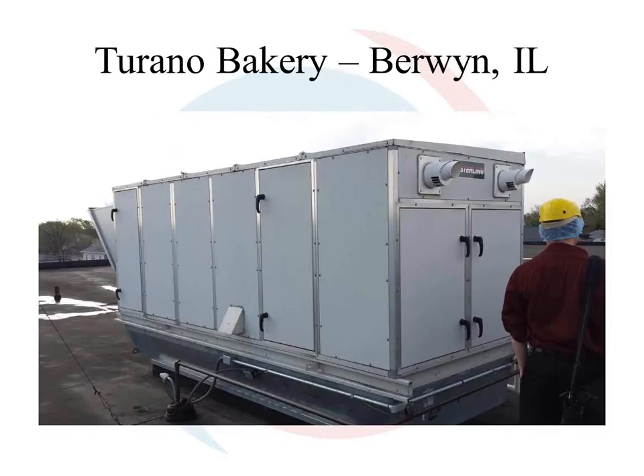Now I want you to notice that the existing curb, they took off the Sterling makeup air unit, and they had to do nothing with the existing opening. There was a curb adapter that had to be made, but it fits right over the existing opening. So with higher efficient, higher capacity units in the 800 to 1.2 million, you don't have to extend or widen the unit and have a huge unit on there. You can use the existing roof penetrations.